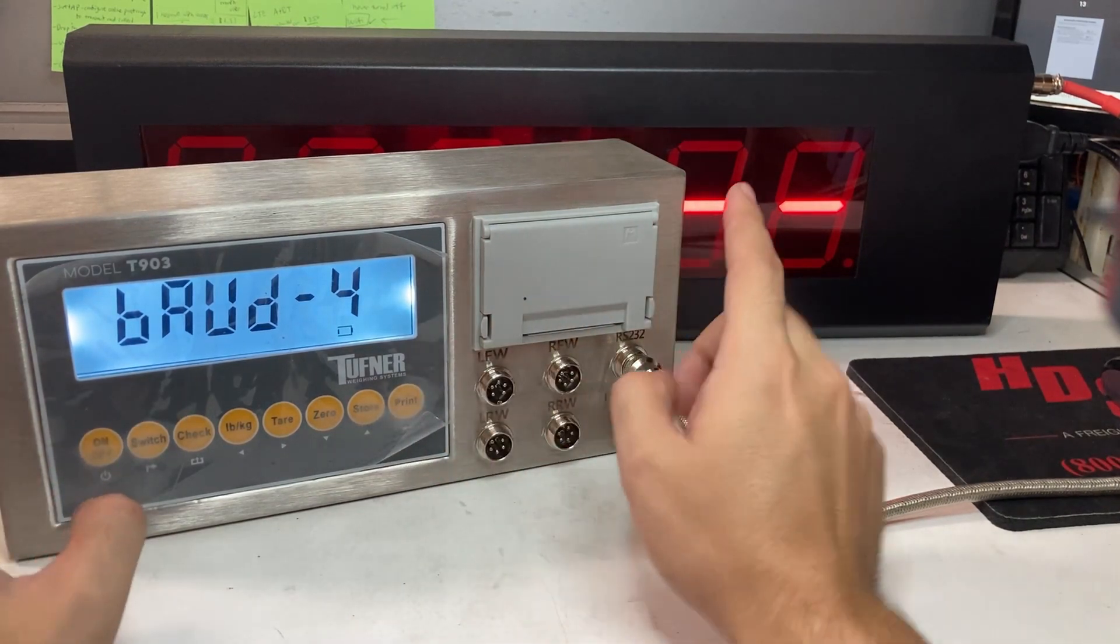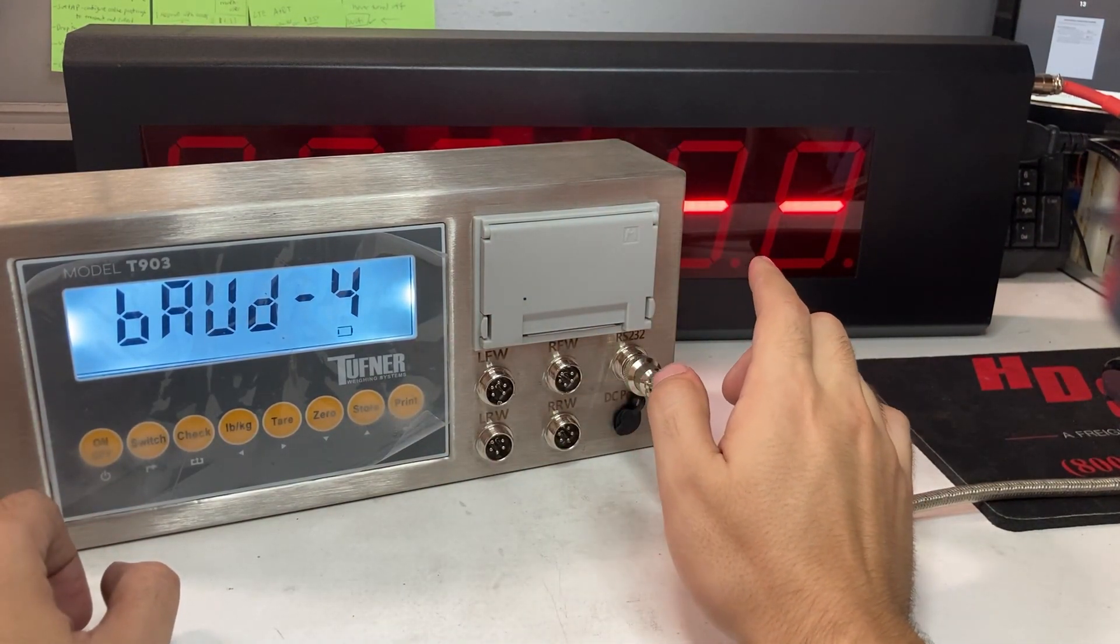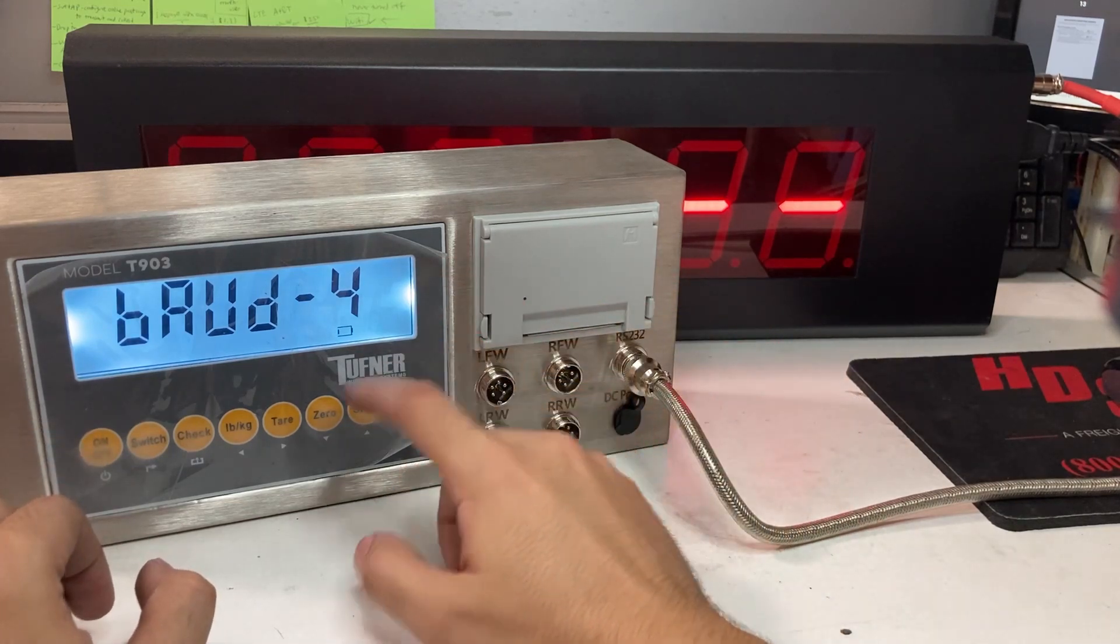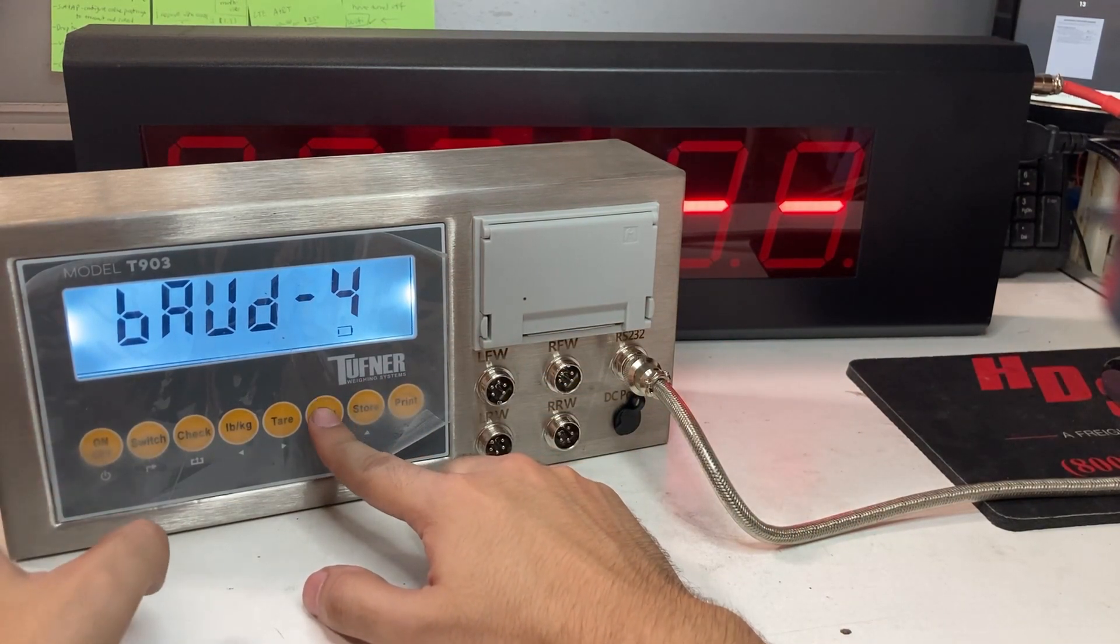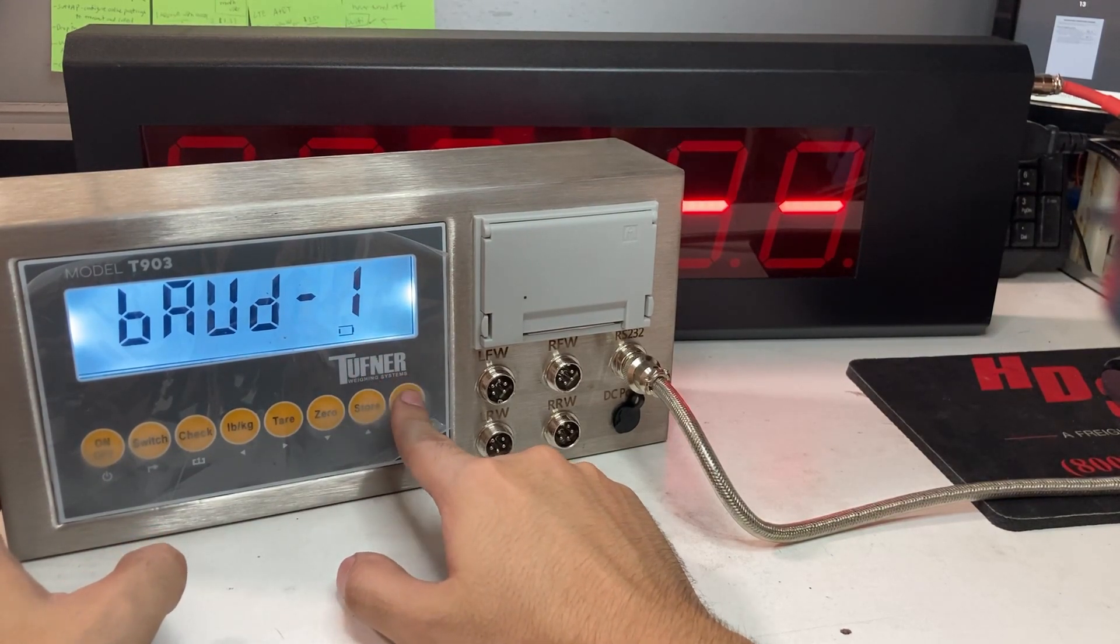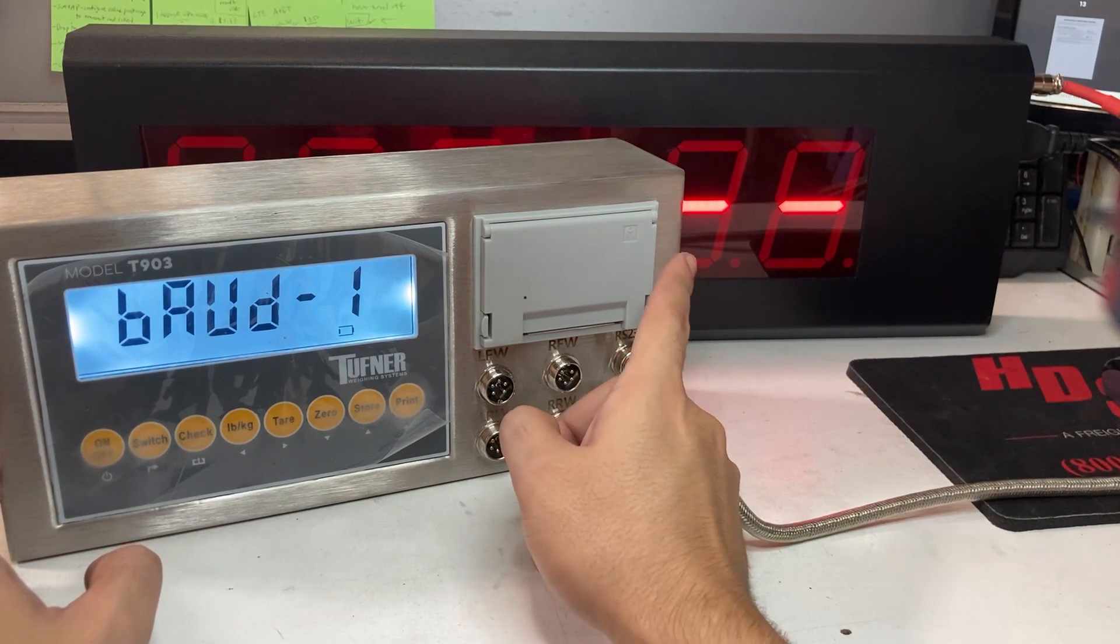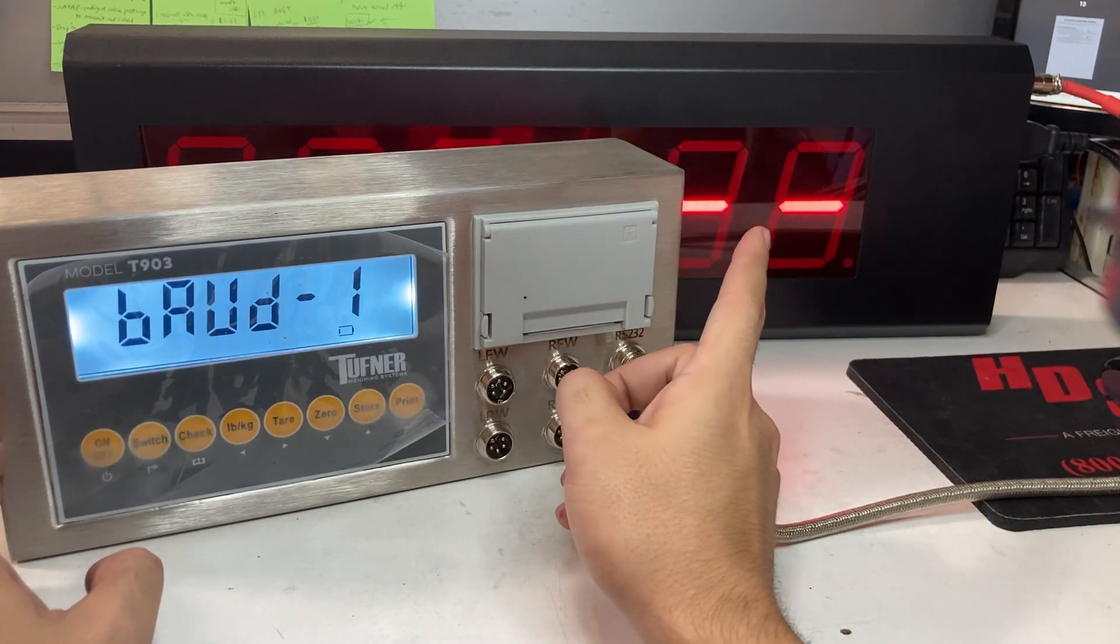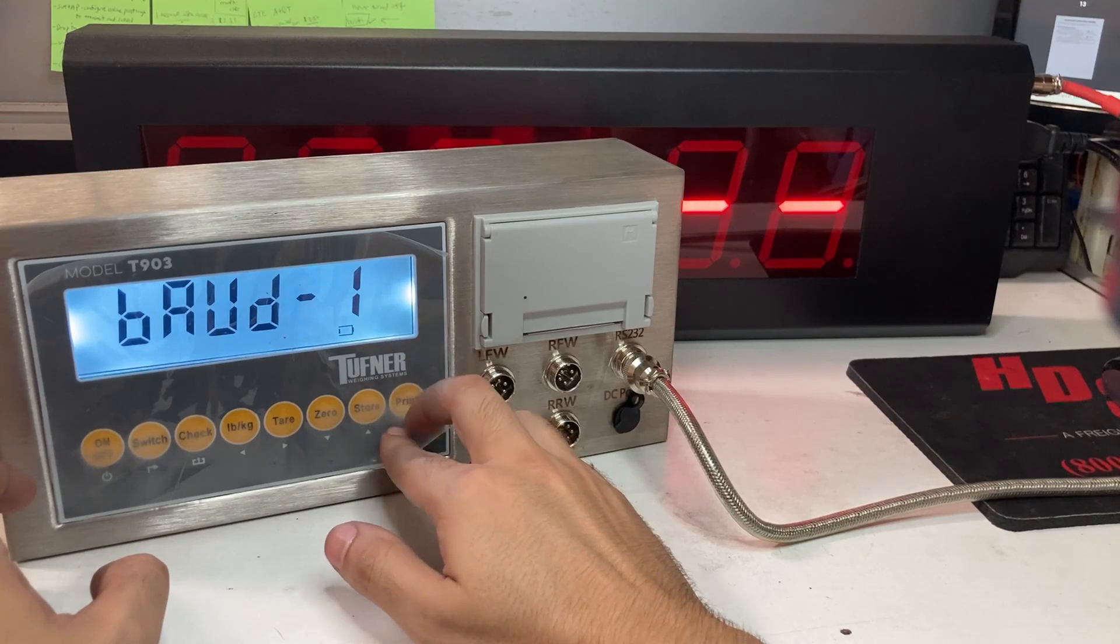This 910, you always have to remember it's a 1200 baud rate. Always remember that. If you look at the manual, a 1200 baud rate is baud of 1. See if I pass it, baud 1. This is specifically for the 910, 3, 5, or 7, but not for the 910X. 910X might be different.